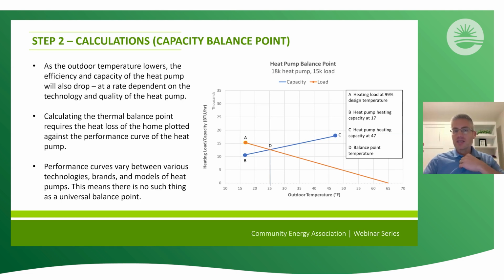And they need to understand that the actual performance of the different equipment varies between technologies, brands, and models. So there's no such thing as the balance point in my area is X or the balance point in my area is Y. The balance point is specific to the house and the equipment being installed in the home. That's a calculated number that contractors should be doing to give you confidence in understanding how low can I run my heat pump? Like, can it cover the heating, or what additional supplemental heating might I need, depending on what I'm able to put into my house? But it's a calculated value.